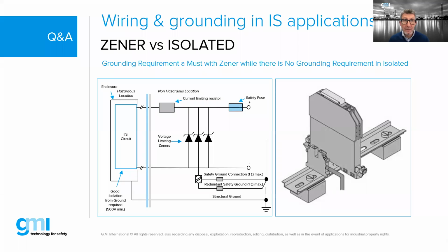Here's some examples. We covered the information on the left-hand side, but on the right-hand side is actually showing a specific mounting of a Zener barrier to a DIN rail. One thing we've seen quite a bit when doing inspections is people mounting Zener barriers directly to the DIN rail, and that DIN rail is mounted directly to the enclosure via metal standoffs, which in turn is connected to dirty earth. So it's really important that if we use Zener barriers and mount them to DIN rails, we make sure that DIN rail is isolated by the use of isolator standoffs from the enclosure, assuming the enclosure is metallic.